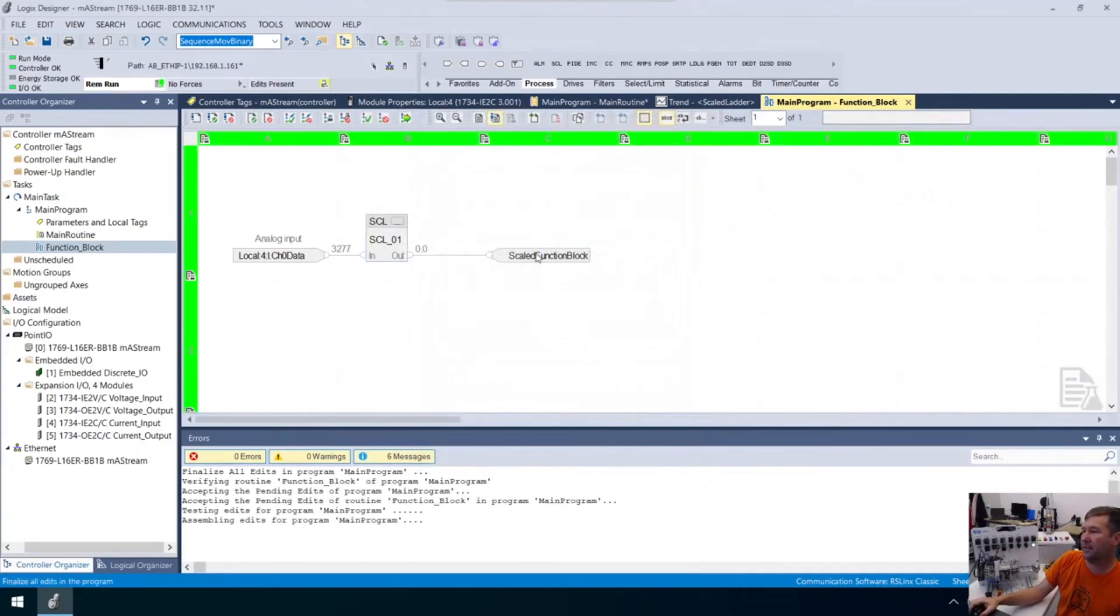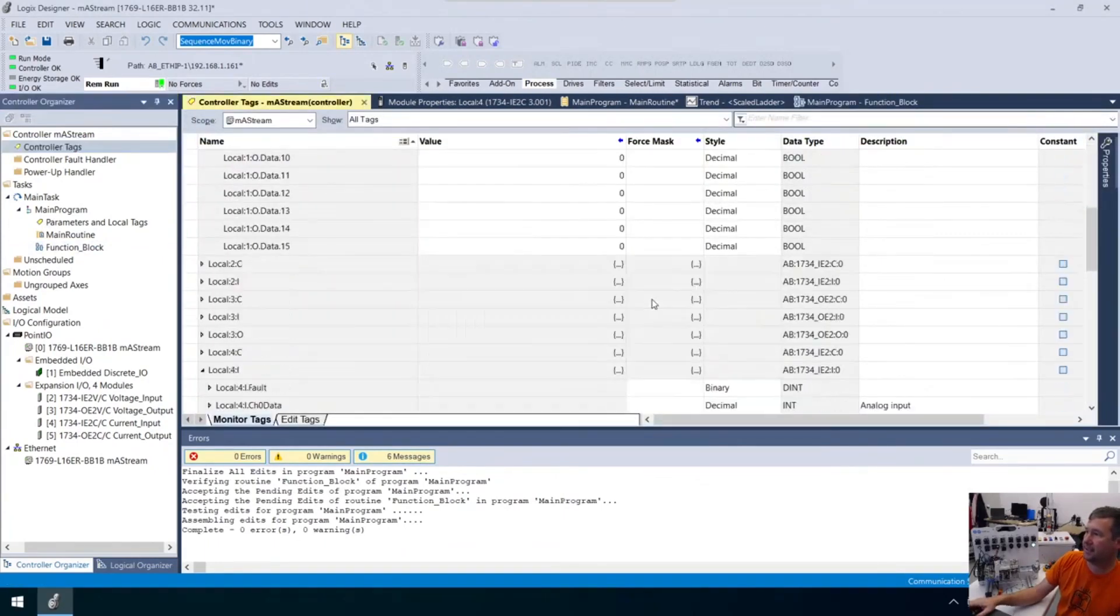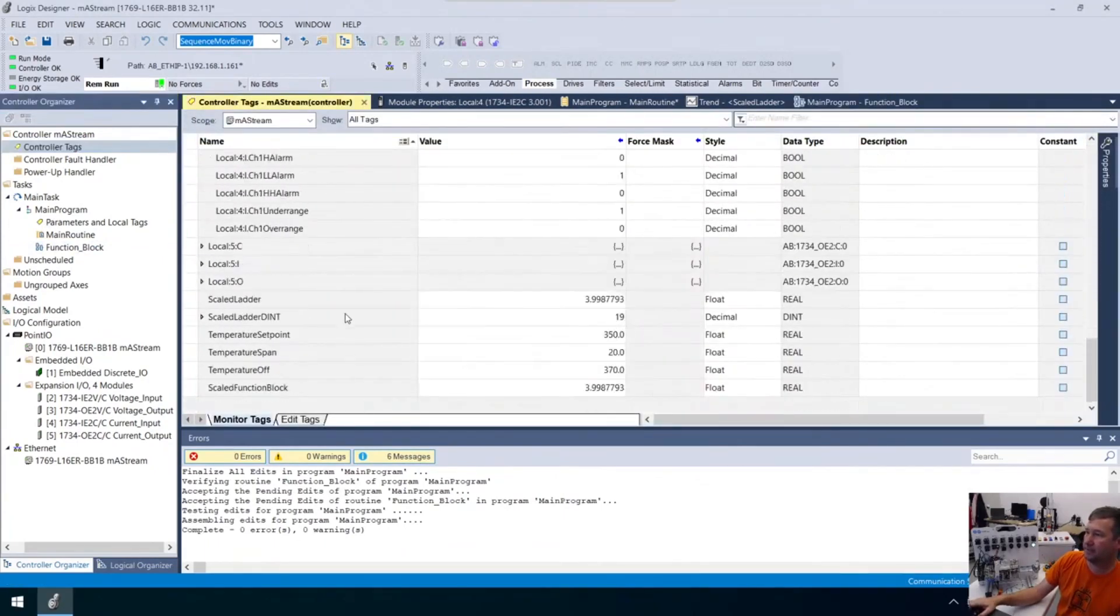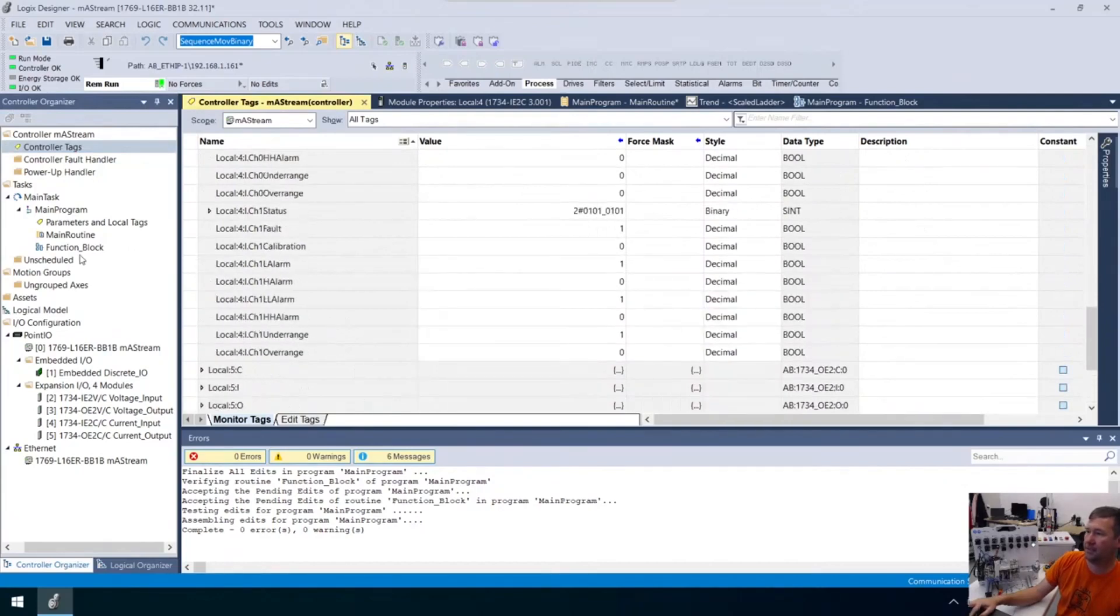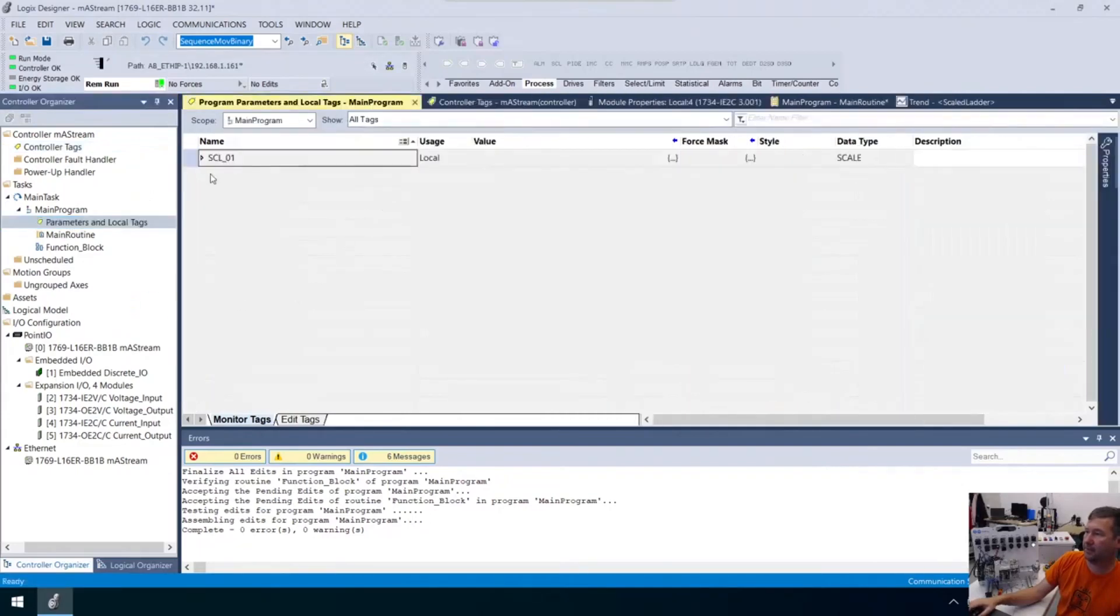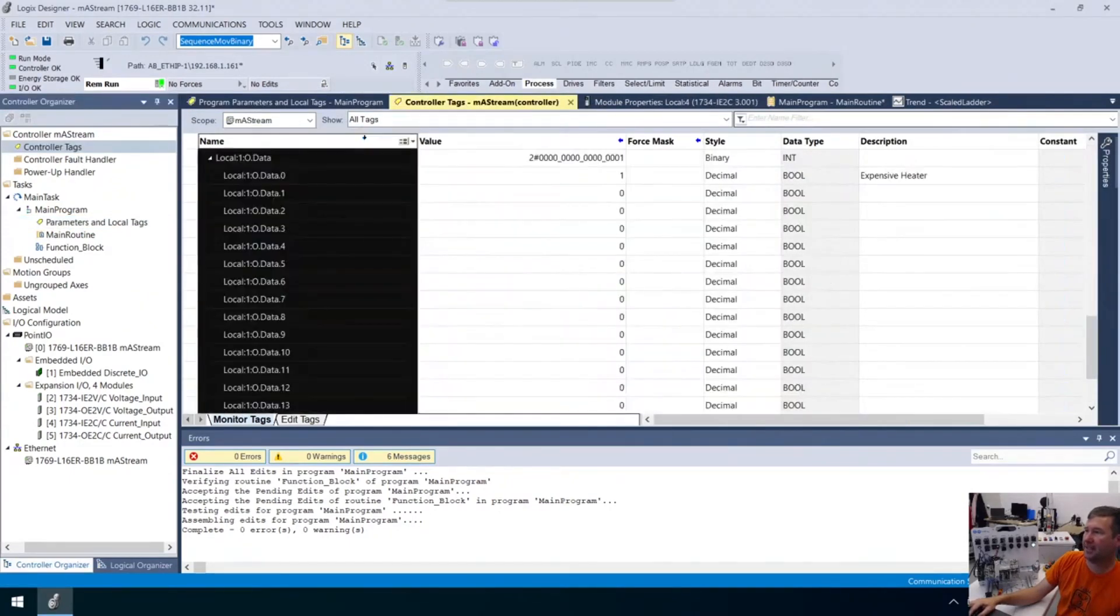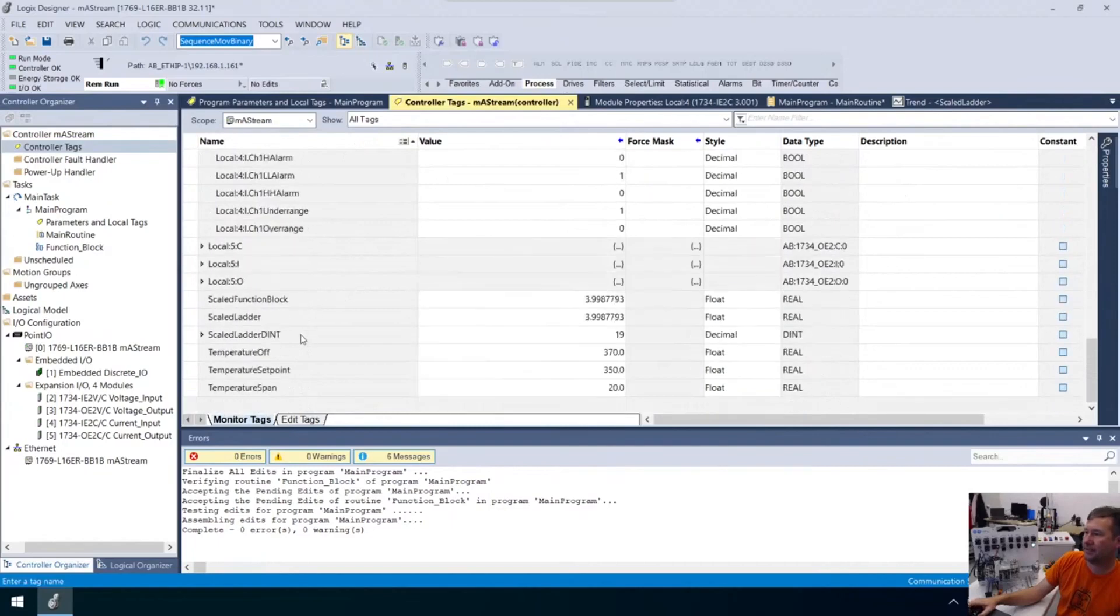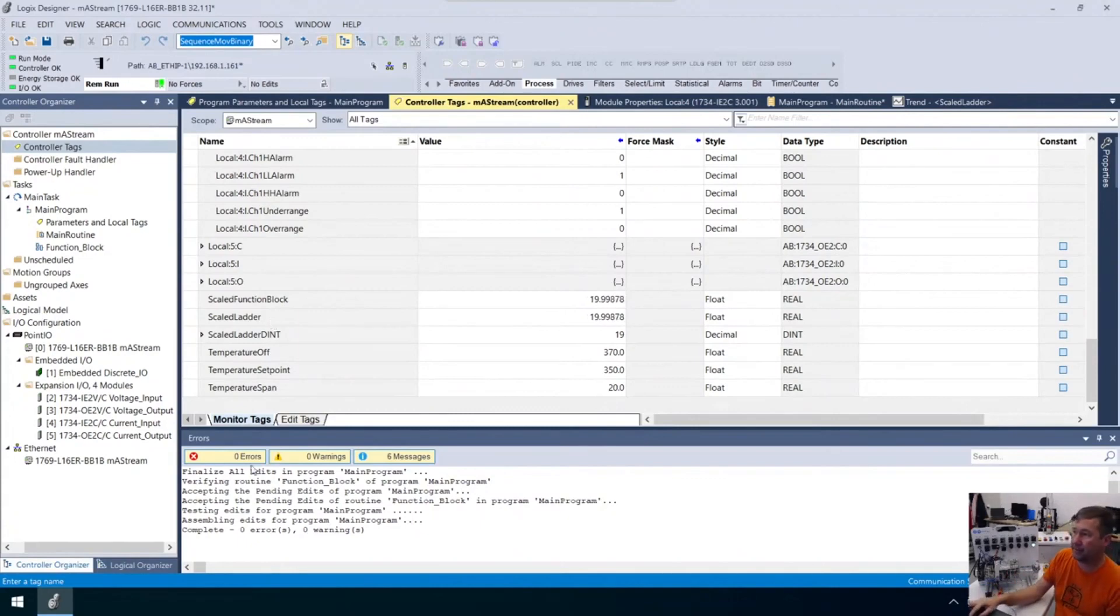We know we're at 4 milliamp right now. We put that in and it's 3.998. Let's open up our controller tags. Notice these numbers, the scaled function block number and the scaled ladder are identical. I'm going to run it up to 20 milliamp and we're right at 19.998. Mainly they're exactly the same.